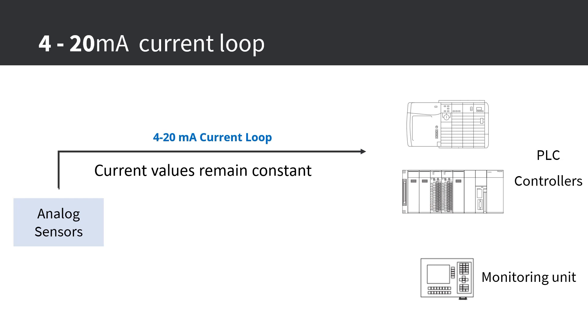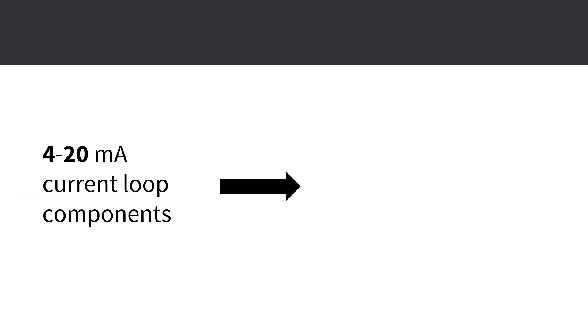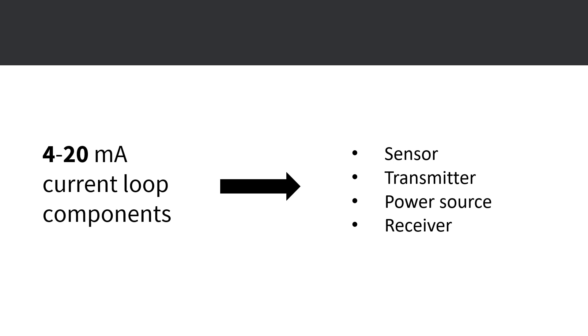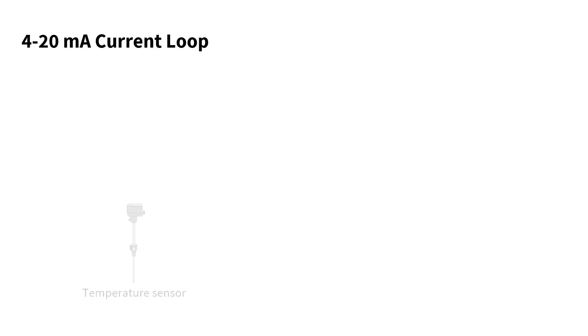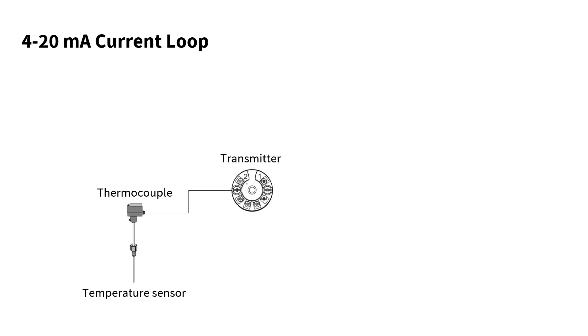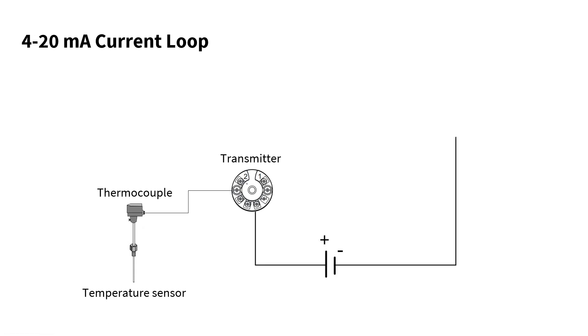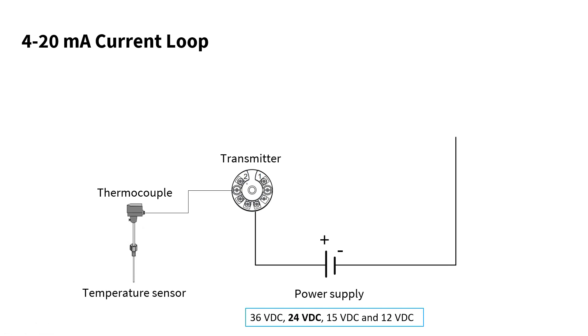A current loop in industrial settings has the following components: sensor, transmitter, power source, and a receiver. A 4 to 20 milliamps current loop looks like this — an example is having a temperature sensor, a thermocouple, to measure a process temperature. A transmitter converts the variable signal from the sensor into current, and the transmitter is what regulates the current in the loop. The power supply provides voltage in the circuit — common voltages are 36V DC, 24V DC, 15V, and 12V, with 24V DC being the most common.